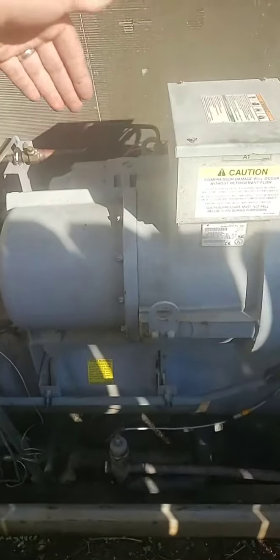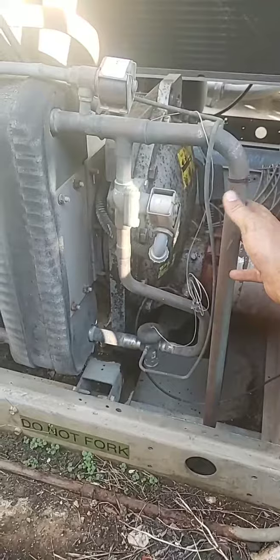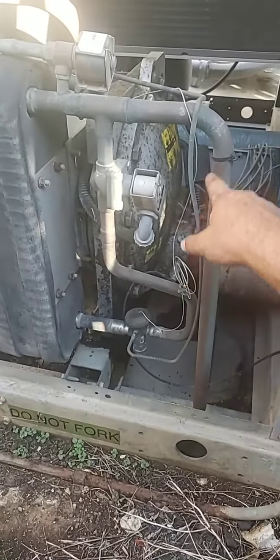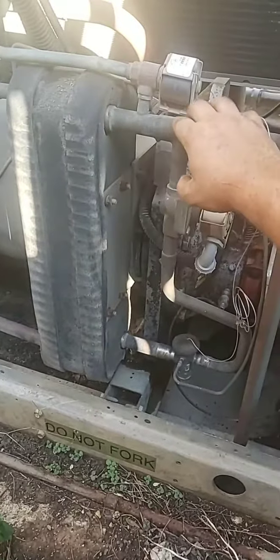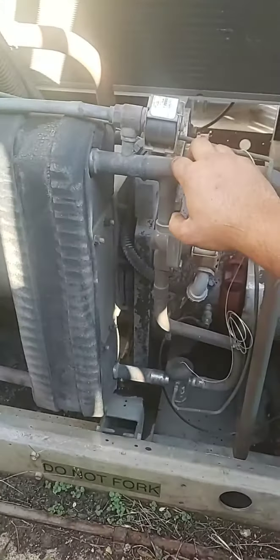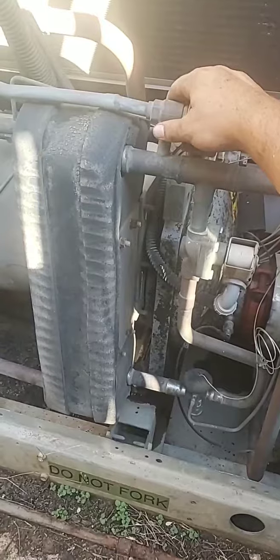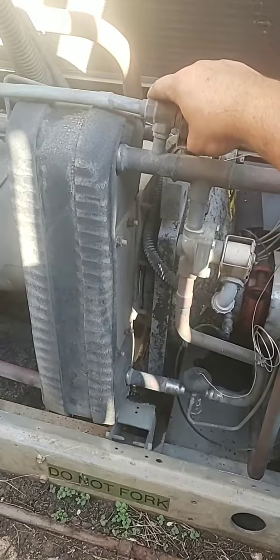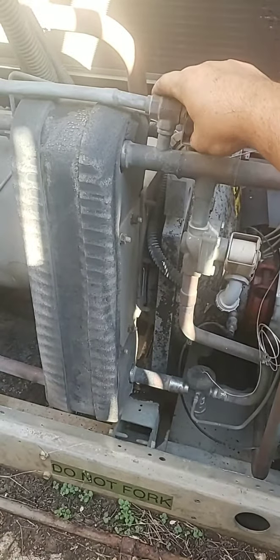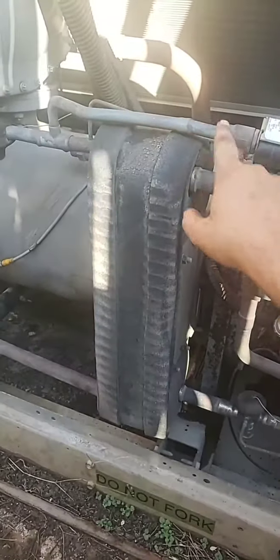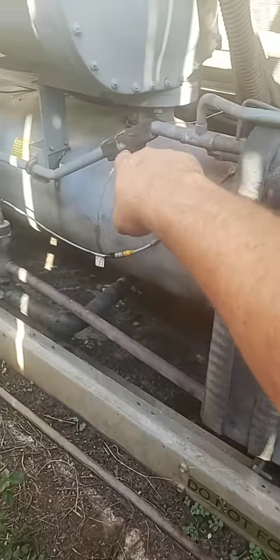Again, it's your motor, the actual screws on the back side, your oil circuit. Obviously, this is going to be your power. So, like I said, this is an air-cooled system. It's got 6 fans on top. Your liquid line comes in right here. So this is coming straight from the condenser, coming up, and then it hits this series of T's. Now I want to take a second to explain this. This T here with the solenoid is the motor cooling circuit. So if you'll see, it comes up and it comes straight off the liquid line, bypasses into that line, which then runs all the way up into the backside of the motor.